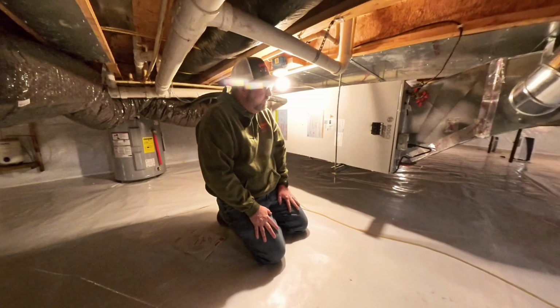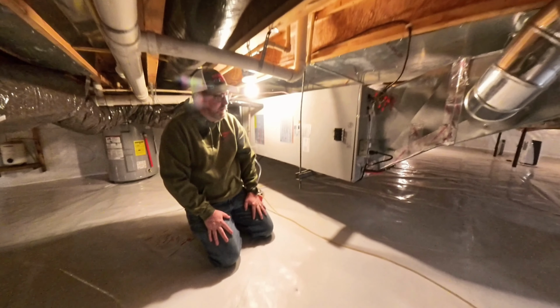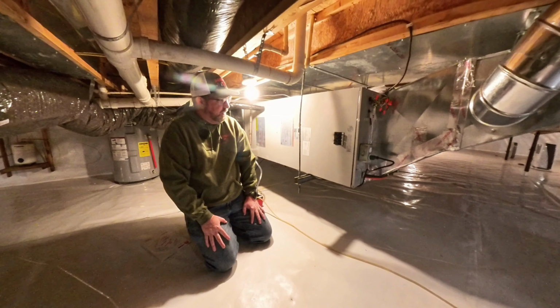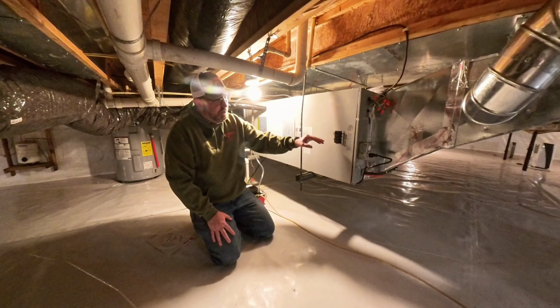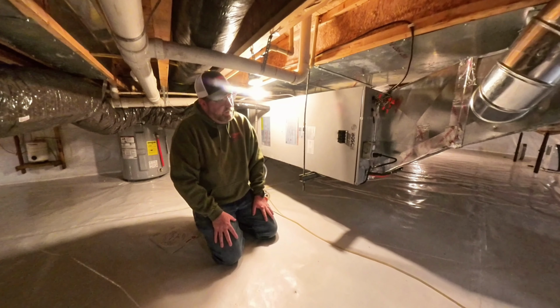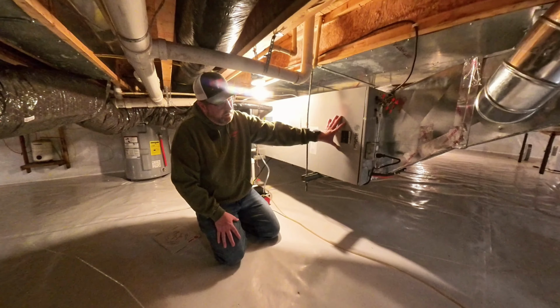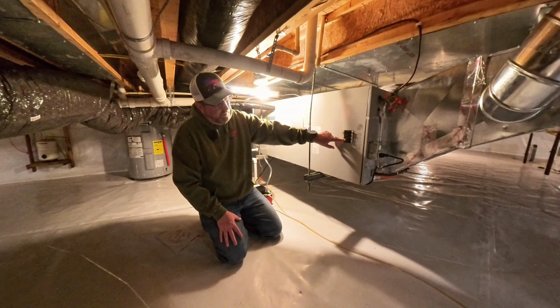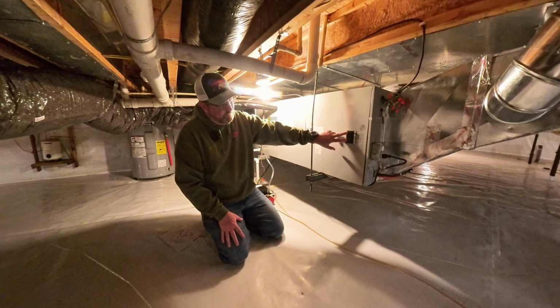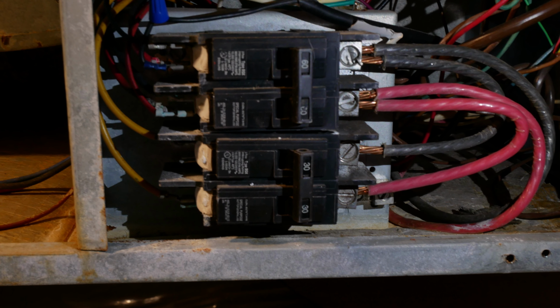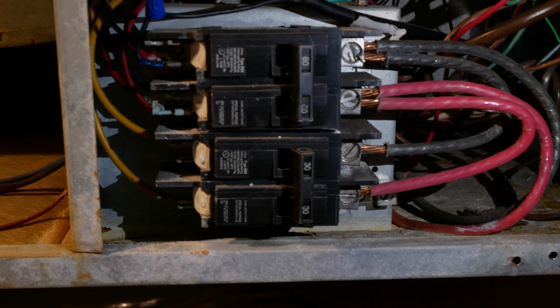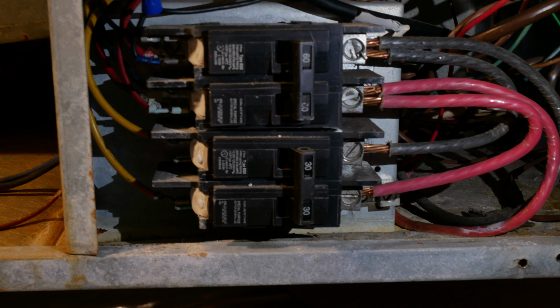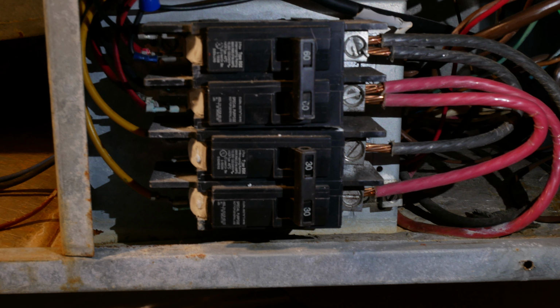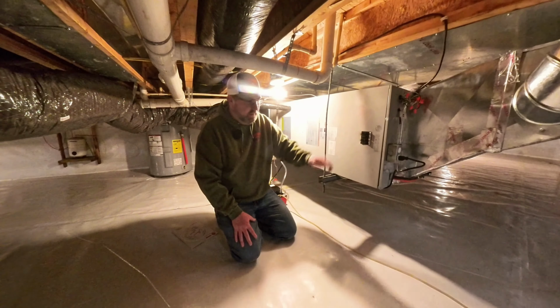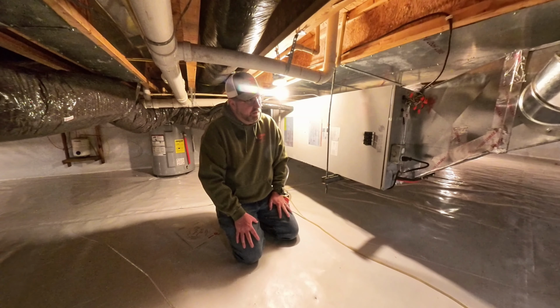Heater kits are sized in kilowatts. There are multiple 5 kilowatt strings inside this heater kit. Previously, the homeowner had a 15 kilowatt heater with 2 different breakers like this air handler does. They had one 6-gauge 60 amp circuit running to the breaker, and inside the air handler they had just piggybacked those 2 breakers together, and that obviously is a big no-no. At that point, that breaker is overloaded.